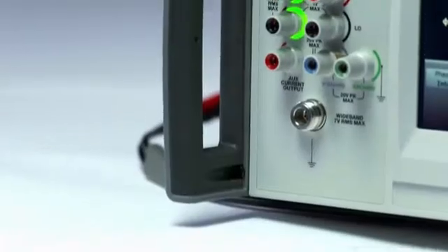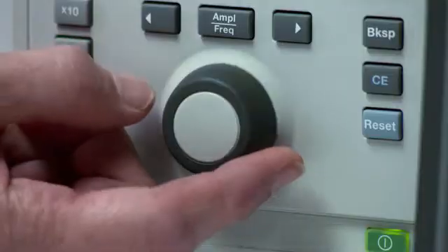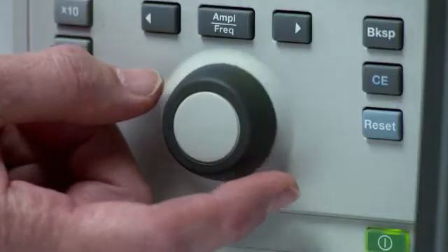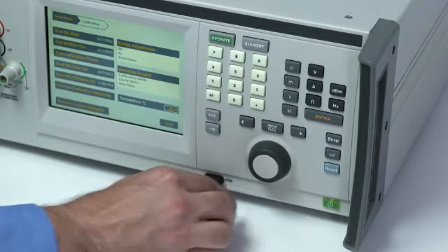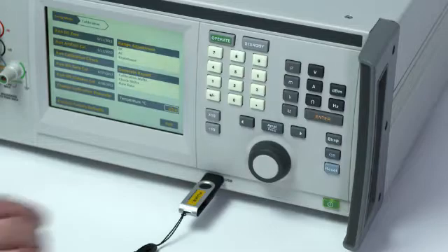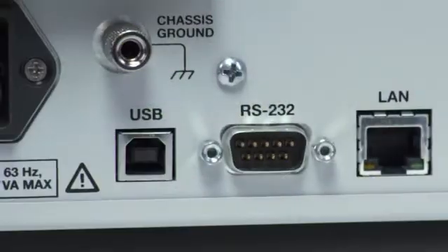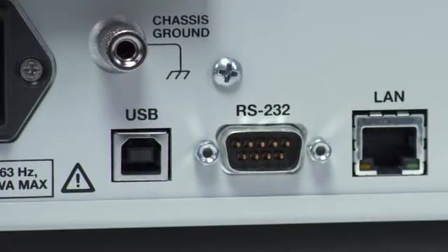The 5730A's handles and spin wheel have been redesigned to improve comfort and feel. USB ports are placed both on the front and rear of the unit. Use the port at the front to download internal calibration constants. Use the rear port for remote connection with a PC.